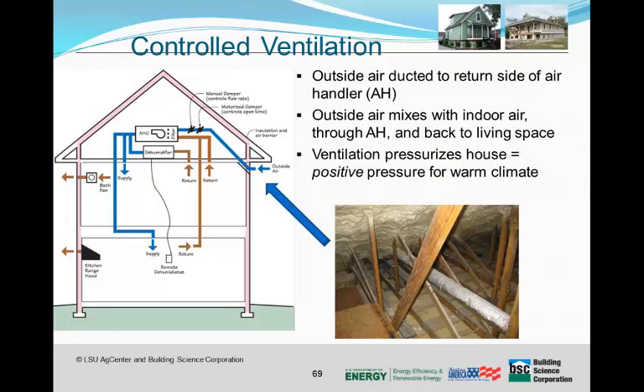Controlled ventilation was provided in these homes. Outside air was ducted to the return side of the air handler from an inlet in the wall under the overhang, a clean air location. Outside air then mixes with the indoor air through the air handler and back to the living space. This provides a slight positive pressure in the house, which is ideal for a warm, humid climate. That slight positive pressure then helps to reduce the incidence and prevent hot, humid air from being drawn through the building and into the cavities and possibly resulting in some hidden condensation.